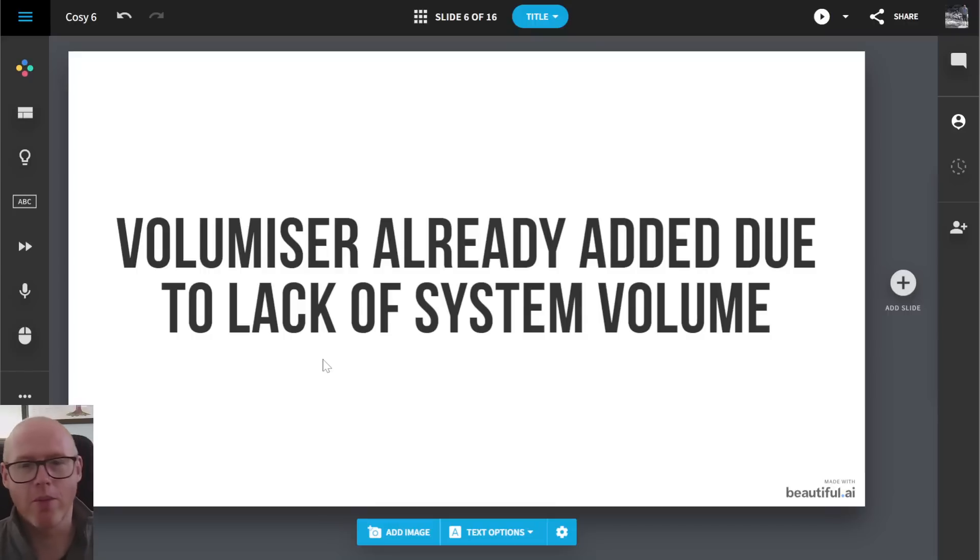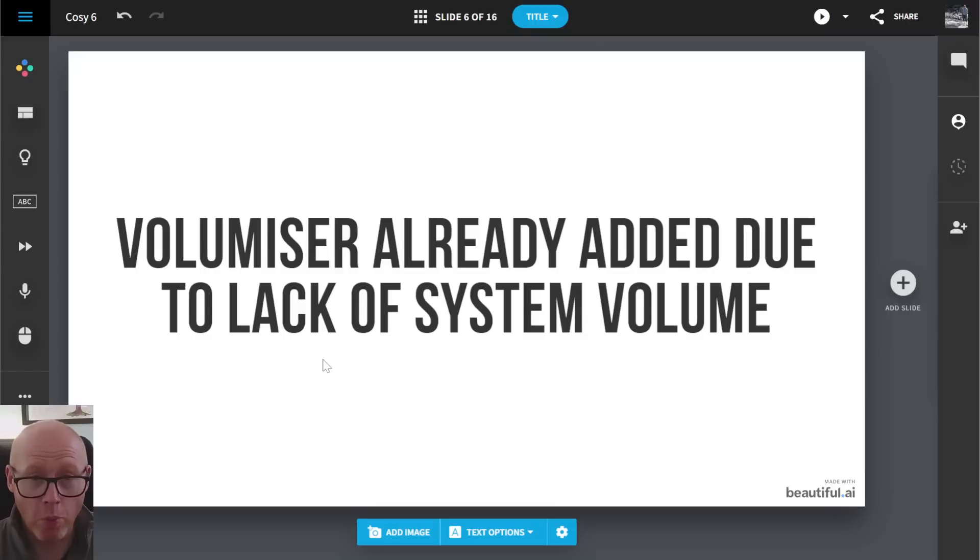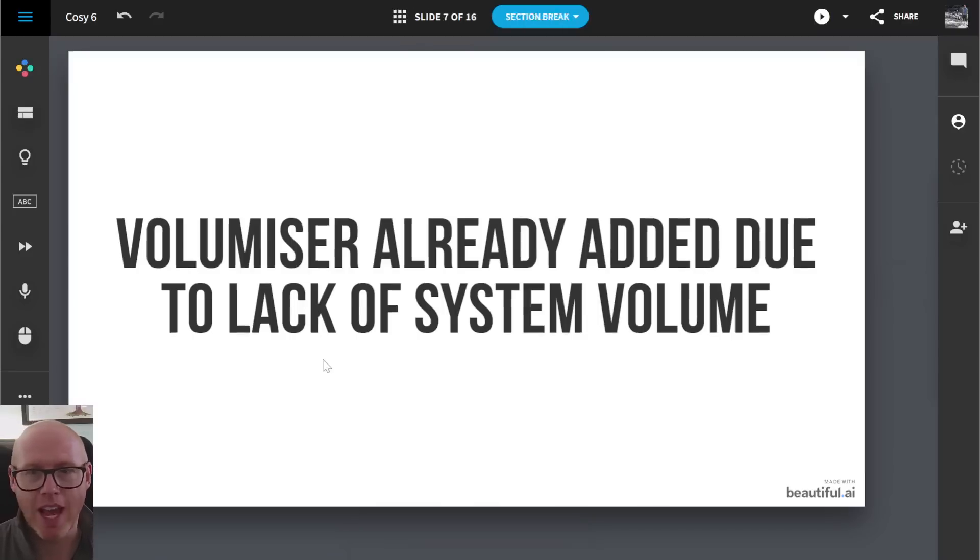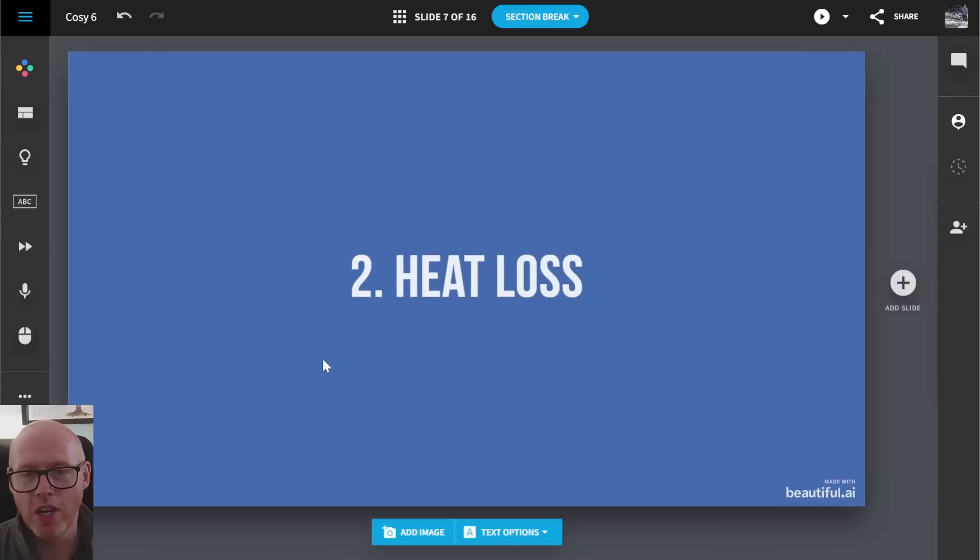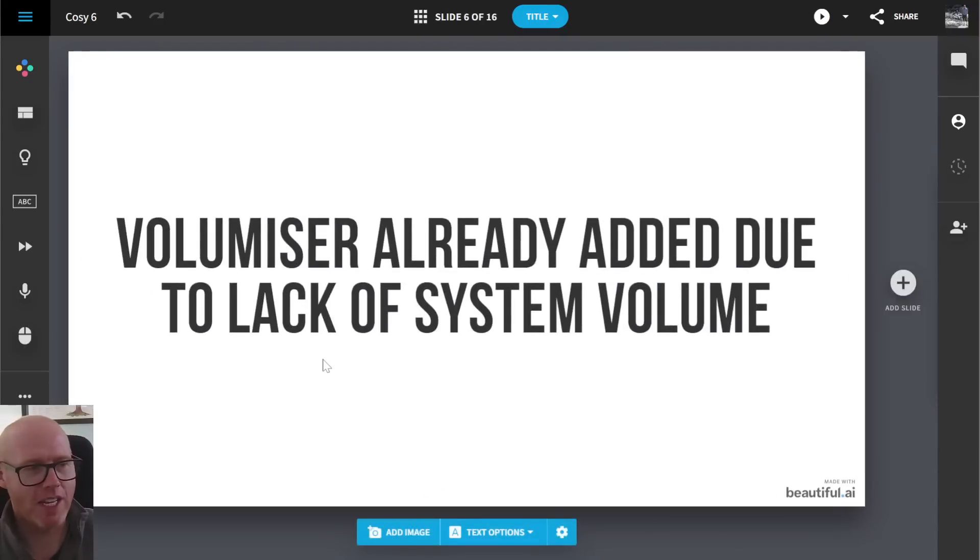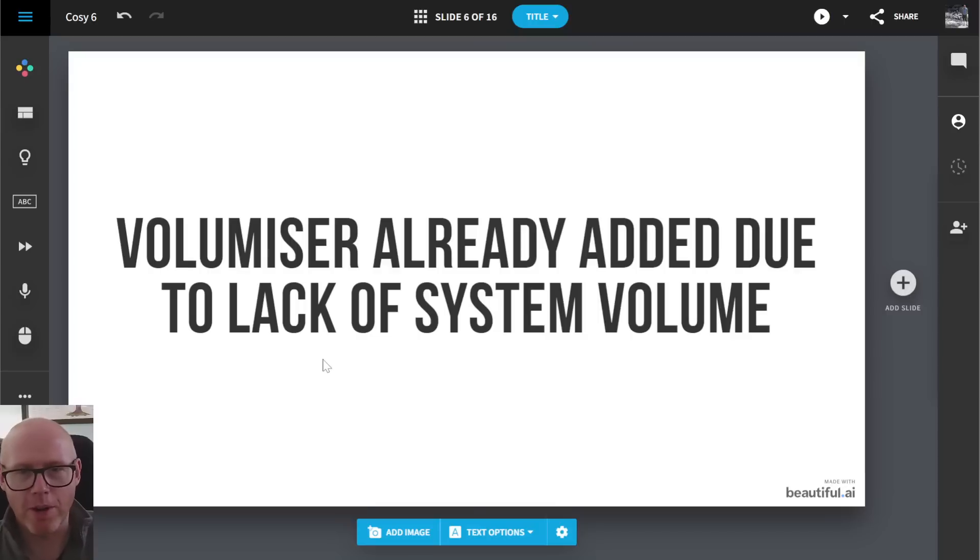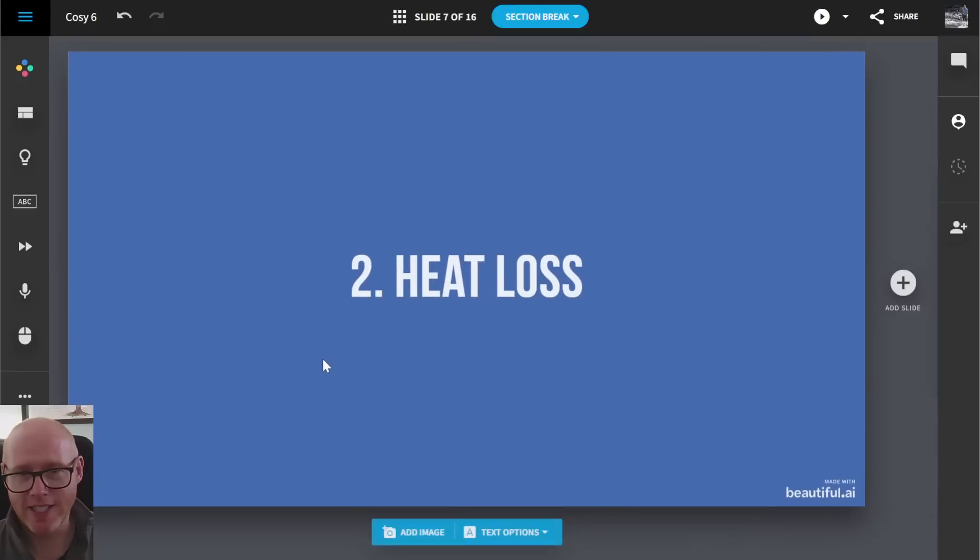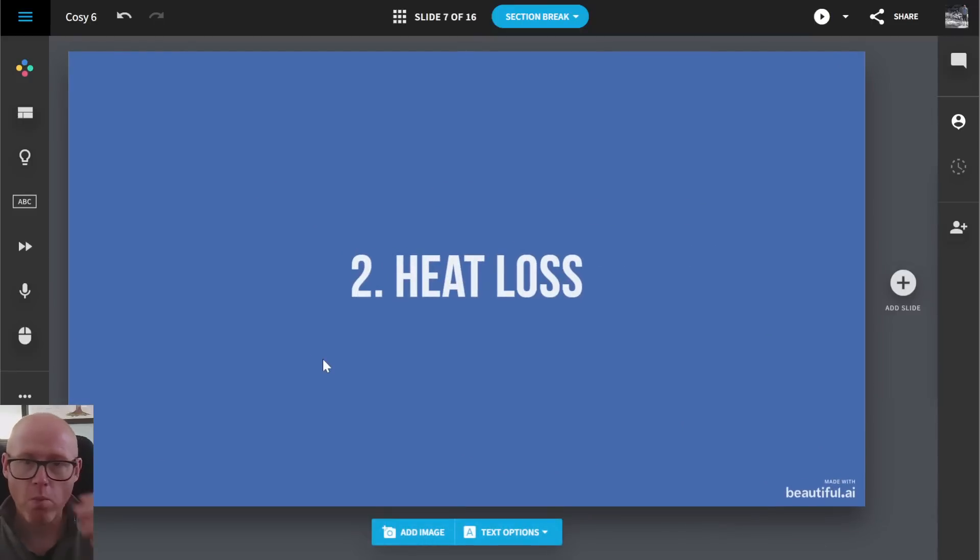House warmth is an issue. So we also learned that he already had a volumizer in the system because Octopus were clearly aware that there wasn't enough system volume in terms of the water, the fluid that's pumping around the system. So they added a volumizer, which I can't remember how many liters he said. Was it 50 liters, something like that? So that's a good couple of decent sized radiators depending on how you calculate and what you're comparing it to.